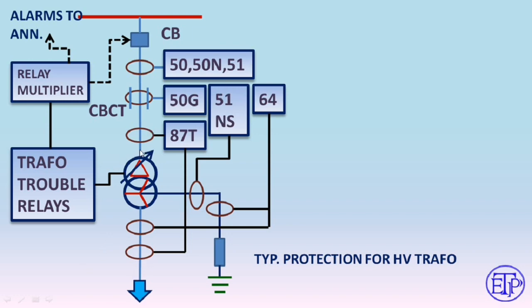For a fault at the high-voltage side of the transformer: if it is a phase fault, relay 50 will instantaneously operate and isolate it. If it is an earth fault, relay 50G will operate first since it is connected with the CBCT and is more sensitive. If 50G doesn't operate, then 50N will operate. Relay 51's functionality relates to the LV side.